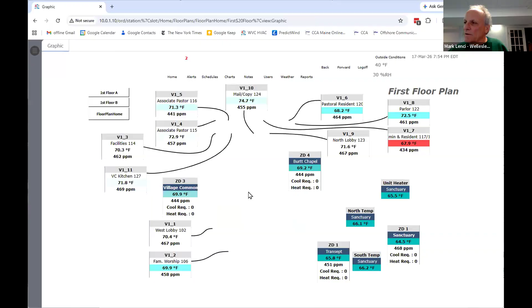Why is it too hot? One of the lessons we learned is that when you get a great control system like this, you actually find out what your HVAC system's doing. We've spent about $50,000 to $60,000 repairing problems in the part of the HVAC system we didn't replace — radiator valves that no longer operated, air dampers that were supposed to move but didn't, thermostats that didn't function. In this office, we had a reheat coil whose tubes were plugged, so it wasn't heating up enough. We went in just 2 days ago and cleaned those tubes, but because of the balance we'd set up when it was plugged, now it's too hot.